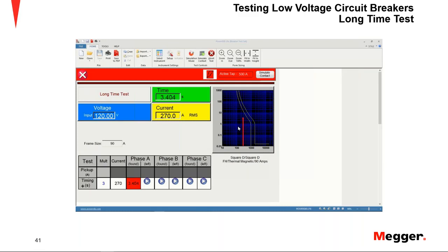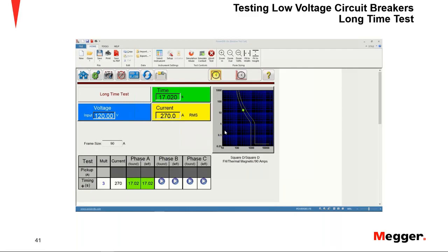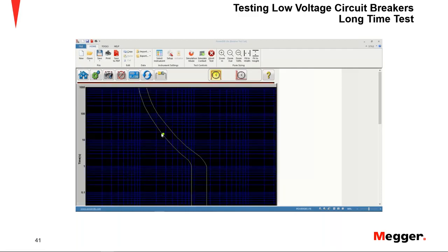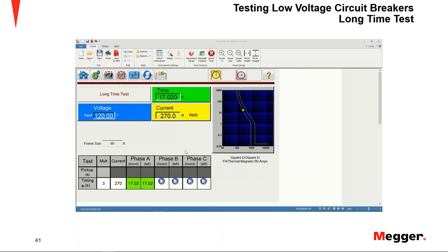Notice in the graph I have live results, so that I have that red arrow representing the current that I'm using and the time. Full disclosure, I made this video using simulation mode, so I will be simulating the trips of the breaker. So notice, as soon as the breaker trips, the software will plot the result in the curve itself. So I will have live values in the curve, so no more comparing with a piece of paper and then guessing exactly where my result will fall in the curve.